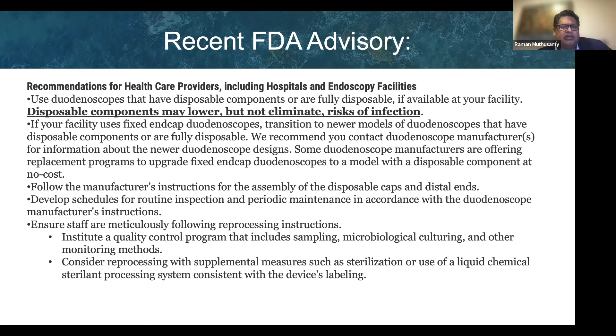So it's not just clinical infections that are relevant, it's also how often a device that we believe to be clean is actually contaminated. The FDA did a fixed end-cap post-market surveillance study, and they were expecting a 0.4% contamination rate with pathogenic organisms, and they found it was 12 to 13 times as high, around 5% for the 2 major models in the US.